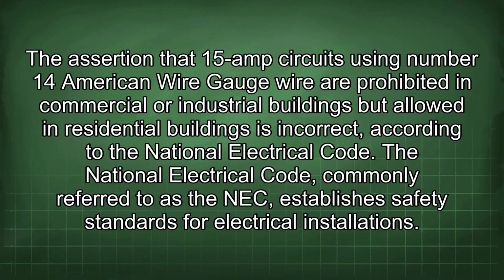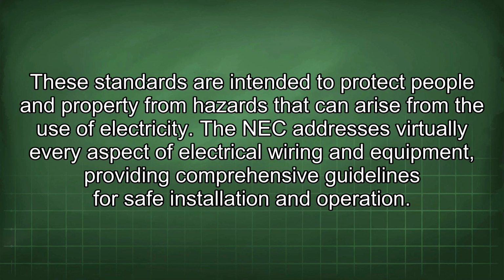The assertion that 15 amp circuits using number 14 American wire gauge wire are prohibited in commercial or industrial buildings but allowed in residential buildings is incorrect, according to the National Electrical Code. The National Electrical Code, commonly referred to as the NEC, establishes safety standards for electrical installations. These standards are intended to protect people and property from hazards that can arise from the use of electricity. The NEC addresses virtually every aspect of electrical wiring and equipment, providing comprehensive guidelines for safe installation and operation.